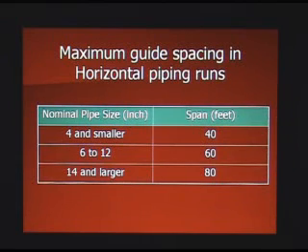On the pipe racks, in this business, usually every support is 20 feet. That's pretty common. But with these sizes, you can skip a couple of supports for the guides. You can go every third one here, every fourth one here, and every second one for this size.